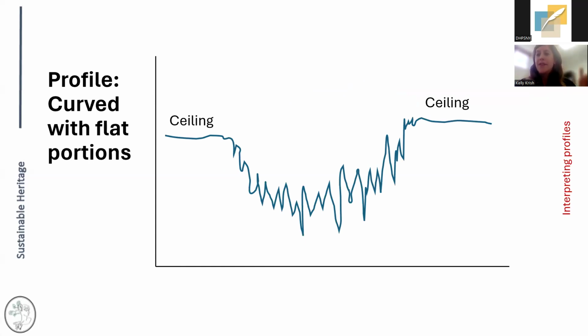If you flip those seasons, if we pretend that the ends of this are the summer and the middle is winter, we're seeing the opposite. So what this is implying is a ceiling. The system is working to keep the moisture levels below a certain point. You can't break through that ceiling, it's staying where it is. So we have dehumidification. We're not allowing it beyond a certain point. What we don't have is humidification. So we're allowing the moisture levels in the space to drop and to coast along with what's happening outside or what our building's able to buffer.